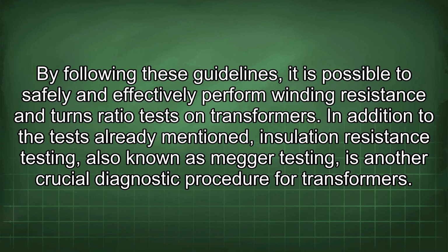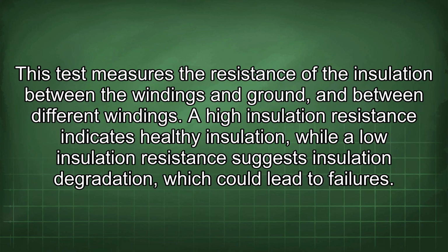In addition to the tests already mentioned, insulation resistance testing, also known as megger testing, is another crucial diagnostic procedure for transformers. This test measures the resistance of the insulation between the windings and ground, and between different windings. High insulation resistance indicates healthy insulation, while a low insulation resistance suggests insulation degradation, which could lead to failures.